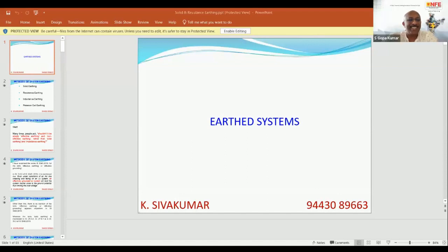First of all, going by IS 3043, going by NEC, going by CEA regulation, the 415 volt neutral must never be NGR grounded. Okay, maybe you have taken special permission and you have put an NGR grounding. Please send me the SLD. I will study and give you the solution.